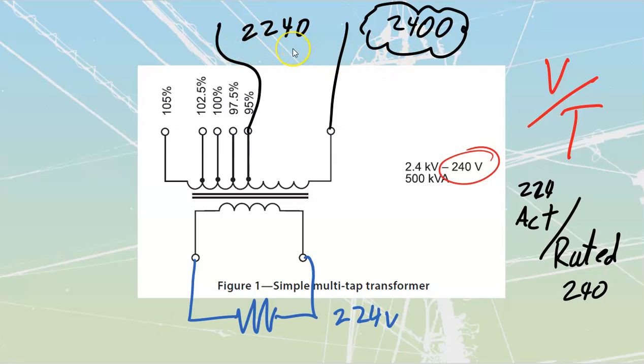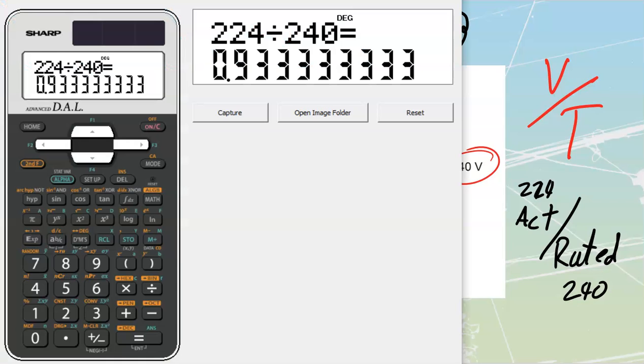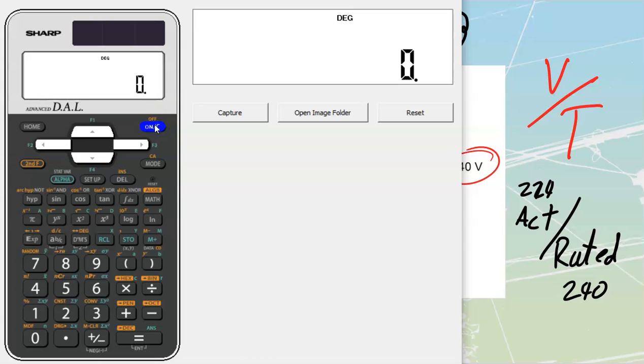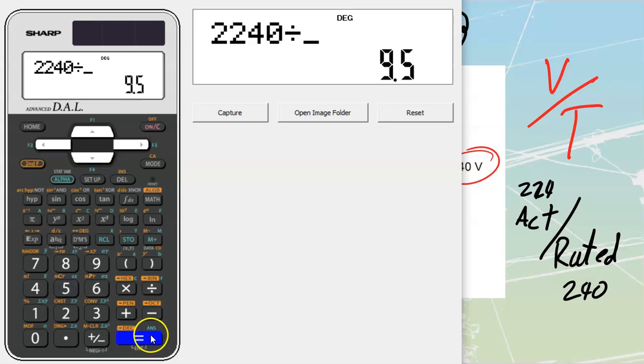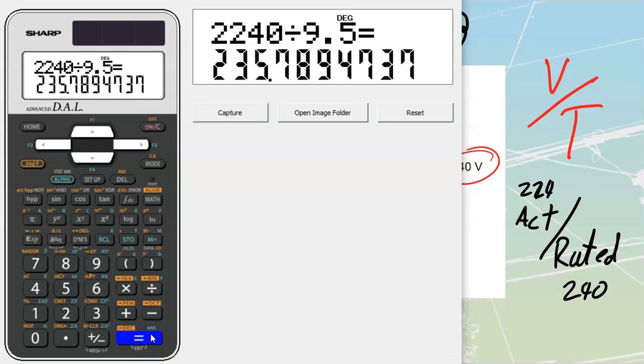We've got 2240 volts. We just did the calculations to get ourselves there. Let's find out what that changes to now that we go to this 95% tap. So we are going to take 2240 and divide it by 9.5, which equals a value of 235 volts. All I did is I took my line in and I divided by my turns ratio.